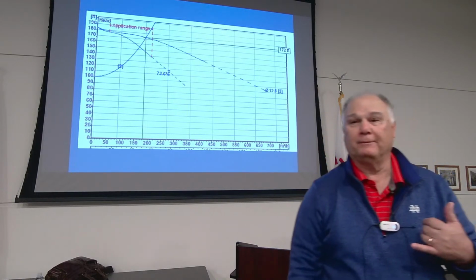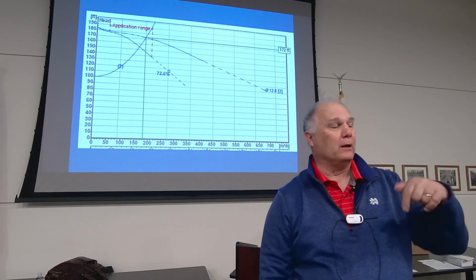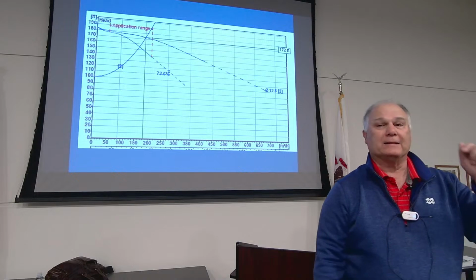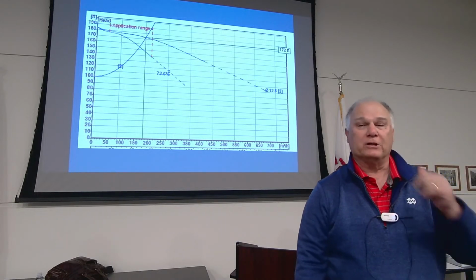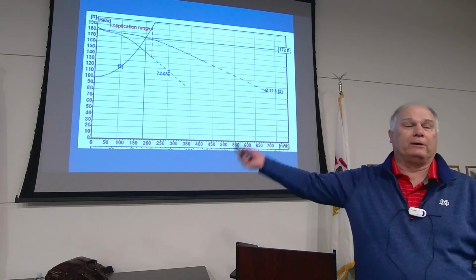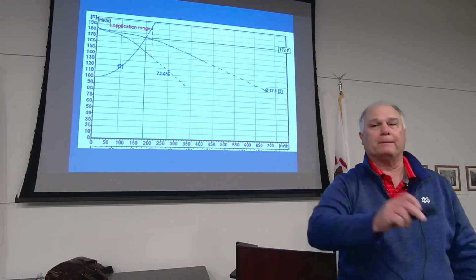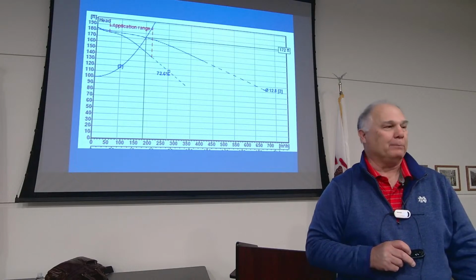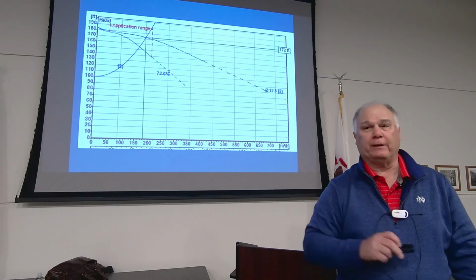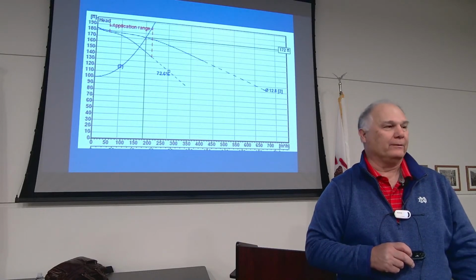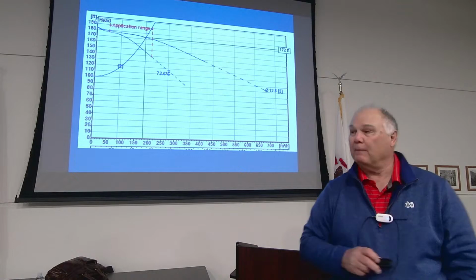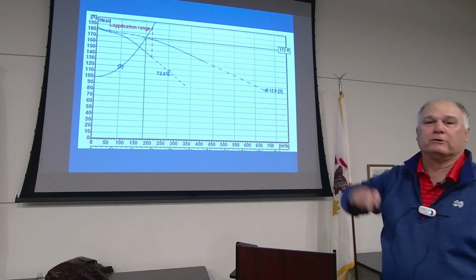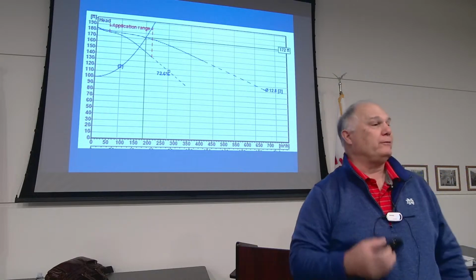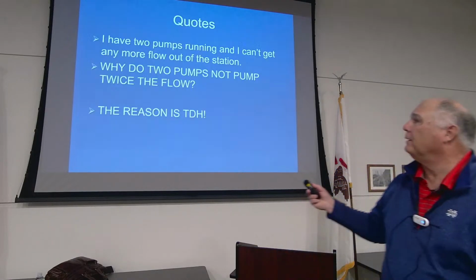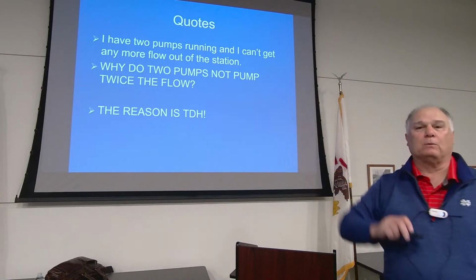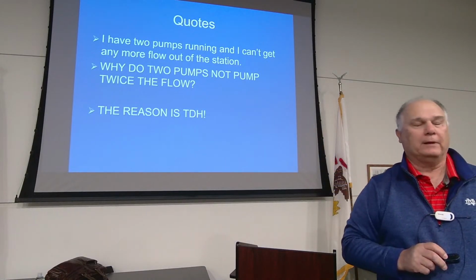Well, that's not true. The reason why that's not true is everybody in this room and online knows today that it is the system curve that controls that. For this particular station, we turn that second pump on, we're going to get a grand total of 110 gallons a minute more volume out of that station. Not a bunch. If we're getting 4 inches of rain a day, 110 gallons a minute is a drop in the bucket. But that's a critical factor, understanding how long your force main is, what your C factors are, and that's the reason why. It's not the pump's fault. It's the TDH's fault.